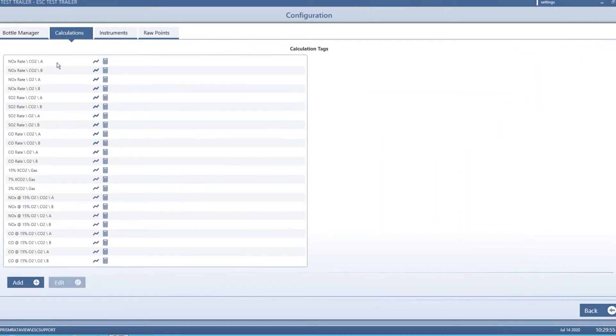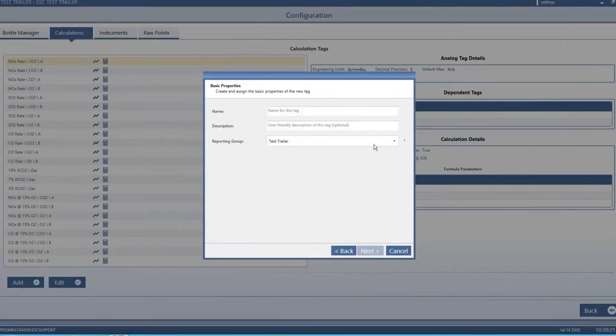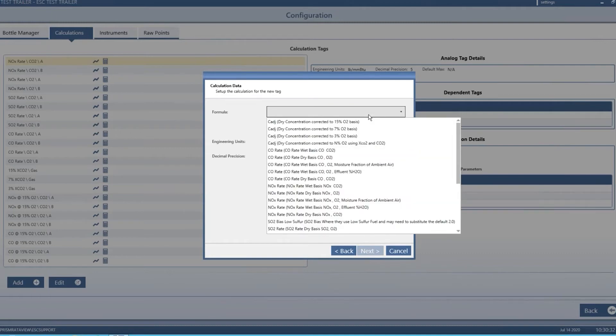The calculations tab allows you to set up additional calculations in the system. The ones typically used for the analyzers configured for your system will already be set up by us upon installation, but you do have the ability to add your own. For instance, we have NOx rate, SO2 rate, CO corrected, and similar calculations already set up. You can add additional ones using a wizard that steps you through — pick from our predefined list of EPA-type formulas that are stored in the system and are not allowed to be edited.